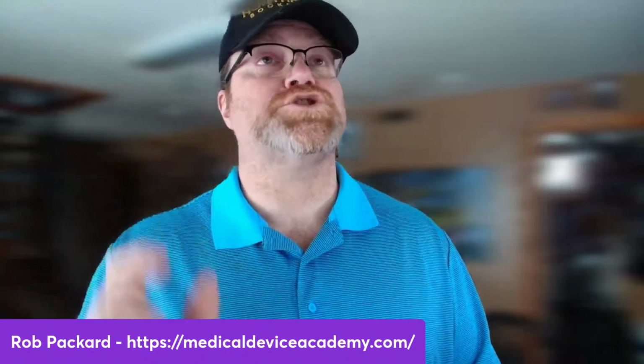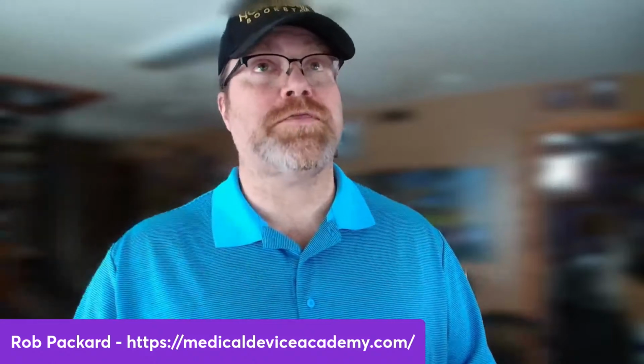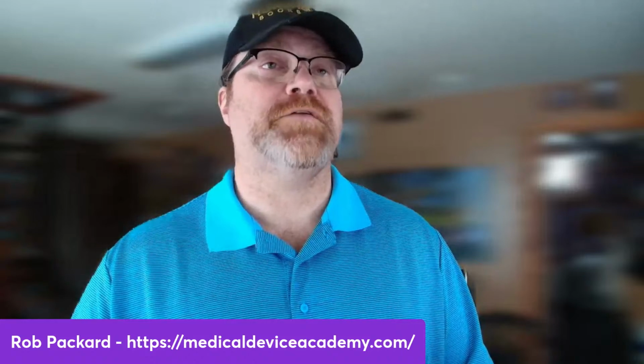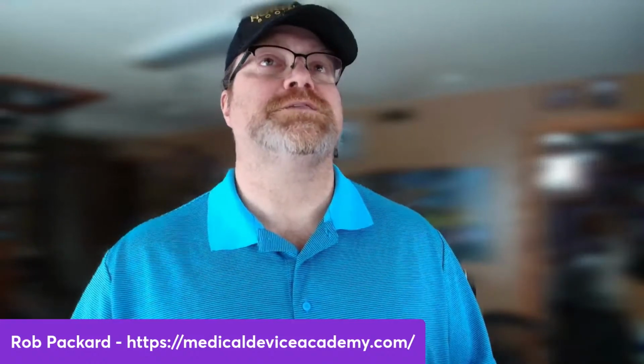But that's one of the things we do. We do a gap analysis of your existing quality system against each of the requirements. And if you don't want to pay somebody to do that for you, you could do it very easily yourself. If you visit our website where we have our turnkey quality system, we actually have a downloadable master document list. Part of that master document list includes each of the requirements for each of the procedures in ISO 13485. So you can see, oh, we don't have that procedure and it's required, or oh, we don't have that procedure, but it's not a required procedure. So that's how that table can help you decide whether you have the right procedures that you need. We sell procedures a la carte, so you could fill the gaps.